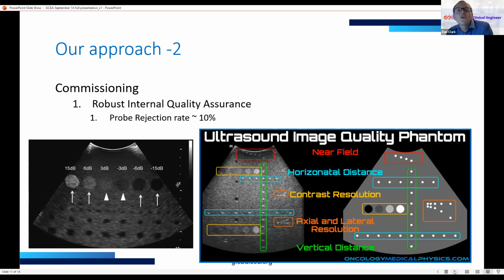So that's 3% on general medical equipment. But it's notable that for ultrasound devices, ultrasound probes, that rejection ratio is very much higher. In fact, it's very much closer to 10%. So nearly 1 in 10 of all newly delivered ultrasound probes fail some aspect of those performance checks at commissioning, and we need to return them or get the manufacturer in to support us and get that put right. So it just underlines the importance of getting those commissioning checks done.